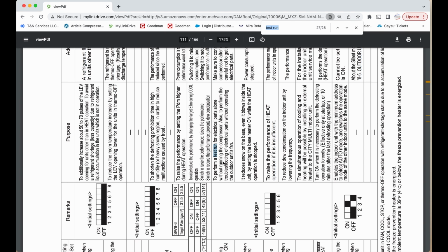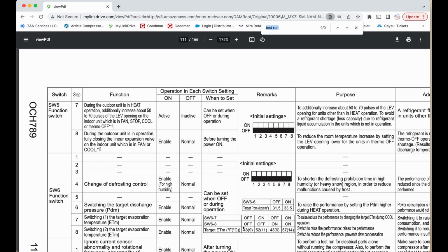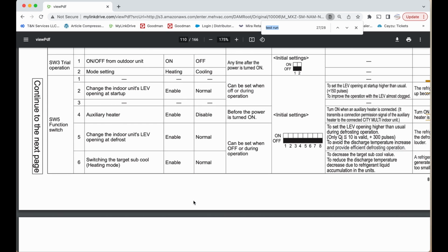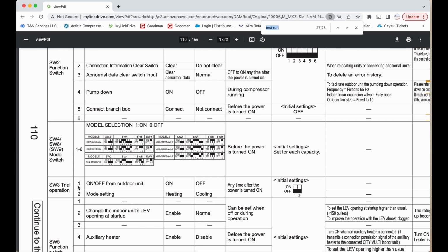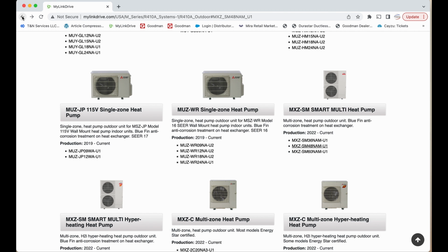Okay, so here's where all the dip switches are. So let me rotate it clockwise. Okay, so we're looking for SW3, SW3 1 and SW3 2. So if you just want to turn it on, you do it just like the P series, only instead of SW4 it's going to be SW3. So SW3 number 1, turn it on, that's going to put it in test run, and SW3-2 is going to be your heating or cooling dip switches. Okay, so that is how you put the branch box system, the P series, or any one of the ducted system that has a wire controller or MHK2 in test run.